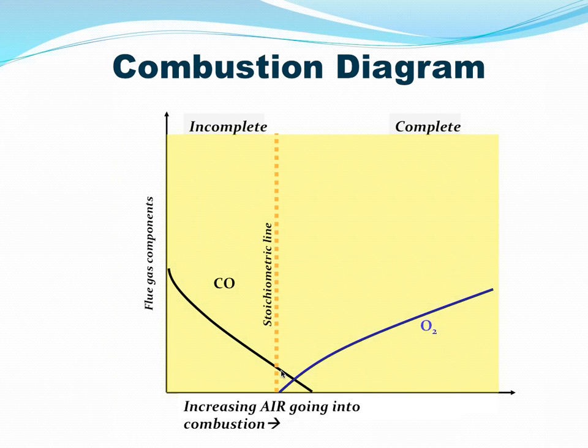That's happening. It should have a higher slope. In fact, I'm going to go back and try to correct that slide using my great PowerPoint skills. But it actually is being diluted here by the oxygen. There's oxygen available, which is going to change the concentration. Again, how much CO is available in the sample is going to be changed here because there's excess oxygen, excess air in the system. So it's going to change this level basically due to dilution of the oxygen.